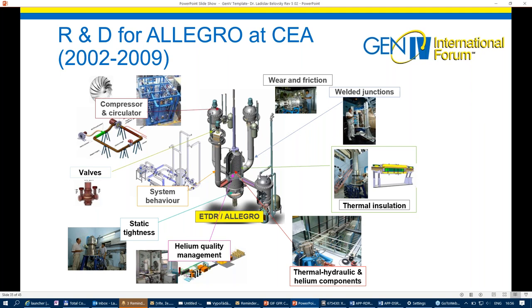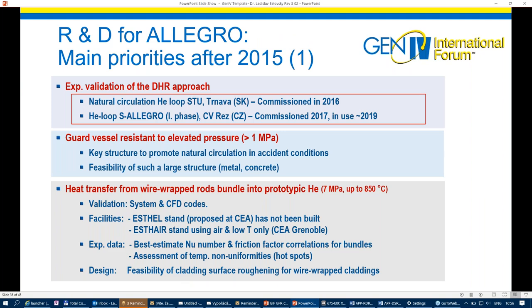The crucial element here is just to ensure the core coolability in passive mode. The R&D priorities are listed here on this slide. The priorities touch the validation of the DHR approach using both loops, which I mentioned already. Then the feasibility of the guard vessel resistant to elevated pressure to provide driving force for the natural circulation.